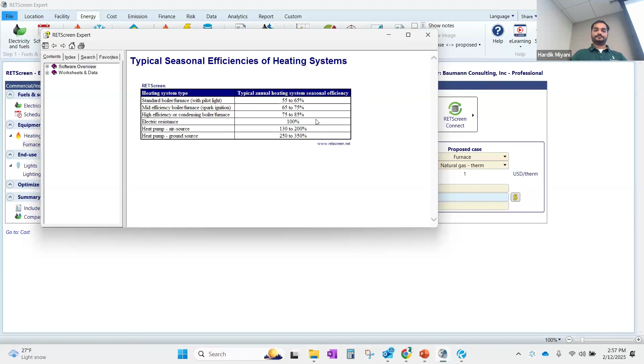You can select this one in blue, and it gives you a very good estimate - a range you can consider depending on what type of system you have: standard, mid efficiency, high efficiency, electric resistance, or a heat pump - air source or ground source. So they've given a good range of efficiency to consider for your analysis. In our case, they've already given 80%, but if you work on any energy audit project and you don't know, you can take this as a reference to get started.